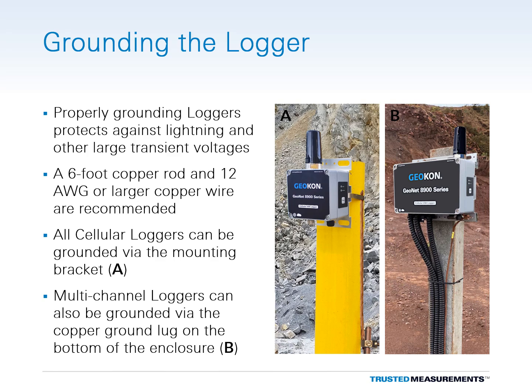Properly grounding the loggers will lessen the chance of them being damaged by nearby lightning strikes or other large transient voltages. Cellular loggers can be grounded by connecting a suitable earth ground to the mounting bracket. Multi-channel loggers can also be grounded via the copper ground lug on the bottom of the enclosure. GEOKON recommends using a 6-foot copper grounding rod with 12 AWG or larger copper wire.